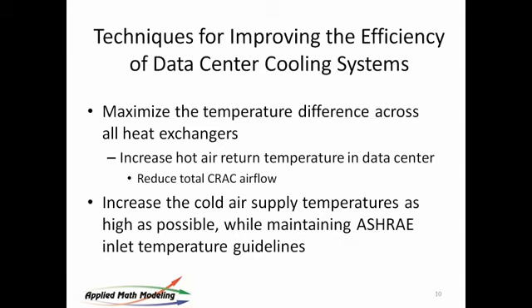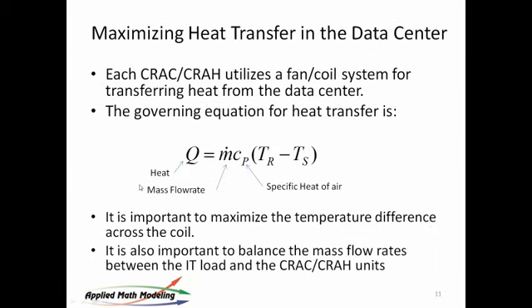You can't increase them too high without typically running into some trouble in the data center, and that's where CFD comes in. So what we do is we try to drive up supply air temp as high as we possibly can without causing problems in the room with respect to the servers. And we use CFD to model the behavior as we increase supply air temperature in the data center. And it's all governed by the same equation. They use a fan coil system on both sides to transfer heat, and therefore the relationship is that heat transfer Q is equal to the mass flow rate times the specific heat of air times delta T.